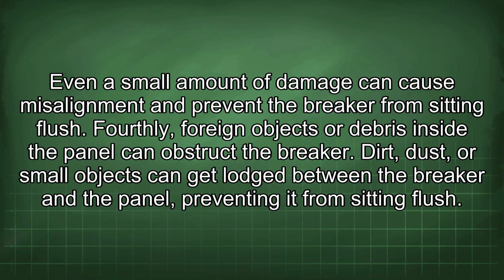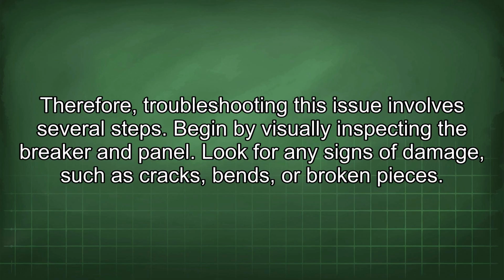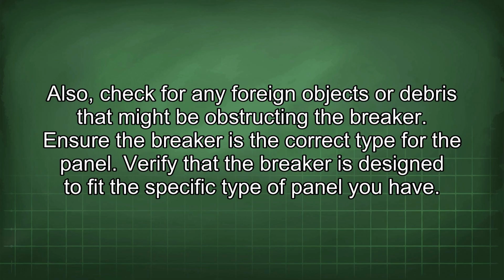Fourthly, foreign objects or debris inside the panel can obstruct the breaker. Dirt, dust, or small objects can get lodged between the breaker and the panel, preventing it from sitting flush. Therefore, troubleshooting this issue involves several steps. Begin by visually inspecting the breaker and panel. Look for any signs of damage, such as cracks, bends, or broken pieces. Also, check for any foreign objects or debris that might be obstructing the breaker.